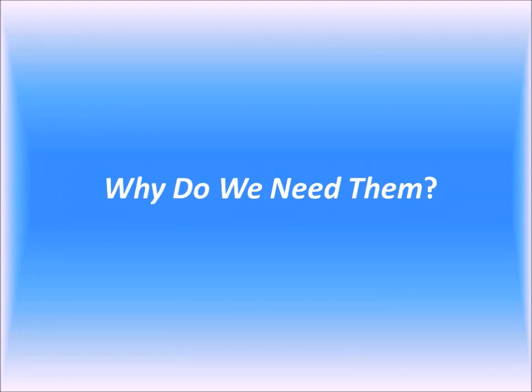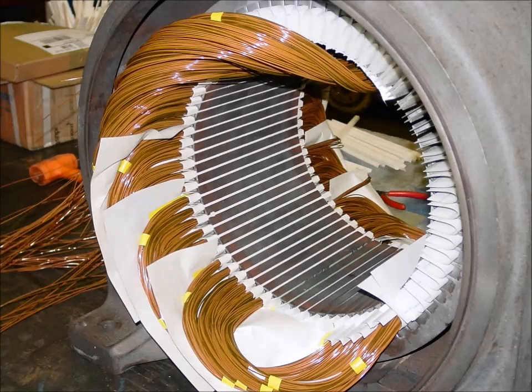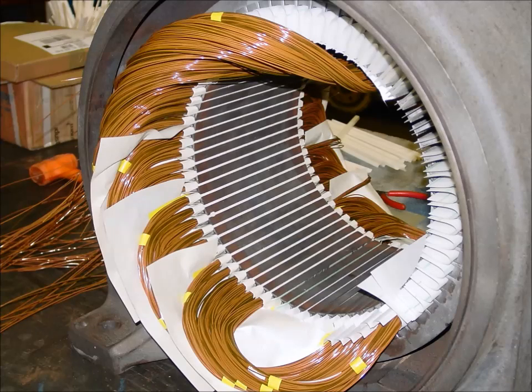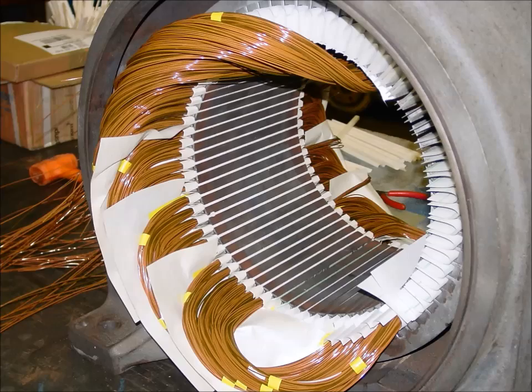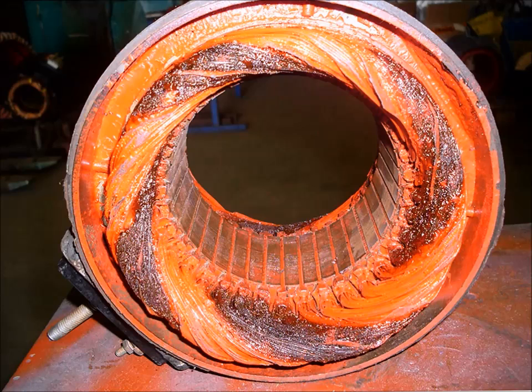But why do we need impregnation systems? Lying at the heart of these electrical machines is the insulation system. Typically, the first and main cause of electrical failure in a motor or generator is due to breakdown of the insulation used for the coils and windings. As the insulation ages, the breakdown voltage of the machine begins to degrade quite substantially. Therefore, ensuring a robust insulation system that can last long enough is vital. The reason for this failure is usually due to the inherently imperfect nature of the material structure as well as irreversible changes due to the aging process.